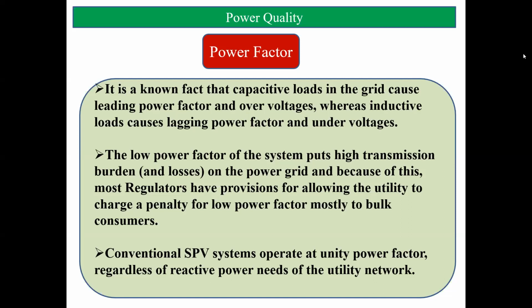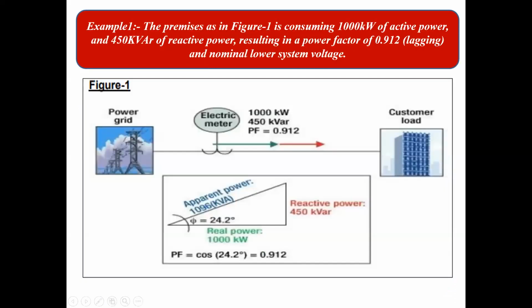Good. With the help of a case study, we will now see how this actual system works. Here in this example, this is a conventional system. On the left hand side you see a power grid, on the right hand side the consumer, and in the center the analysis of the power factor. Here our system has a power factor of 0.912. In this case study the premises has a 1000 kilowatt load, and the reactive power the system draws from the conventional grid is 450 kVAR. The real power is 1000 kilowatt, and the power factor is 0.912.